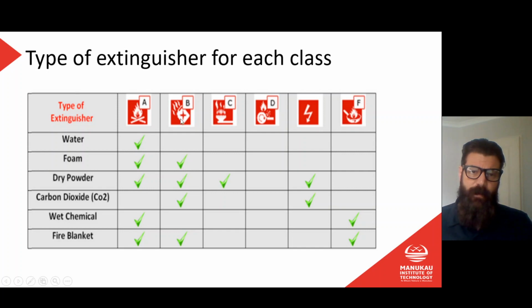So you should see on fire extinguishers these kinds of symbols that will tell you what fires that particular fire extinguisher is useful for. And if you look here, it tells us which type of extinguisher we can use on each type of fire. So for a Class A, those freely burning materials, we can use nearly all of them except probably carbon dioxide. For your fuel type fire, we can use foam, dry powder, CO2, or a fire blanket.